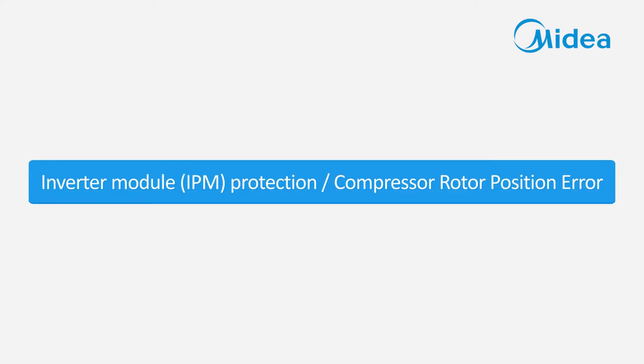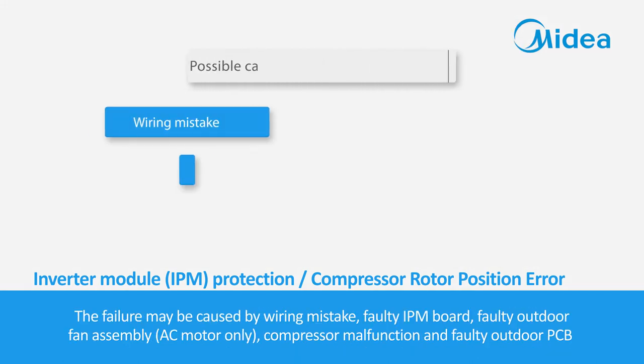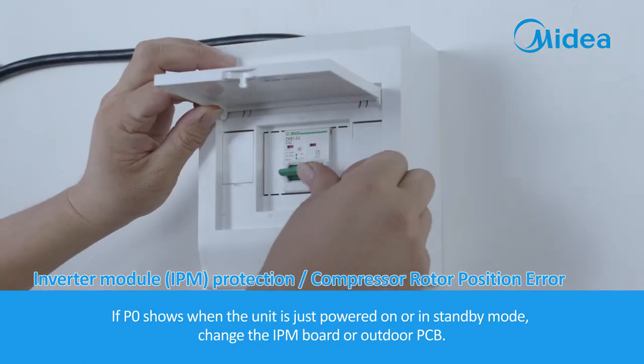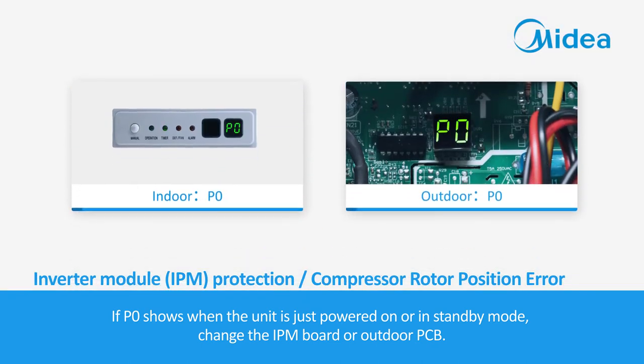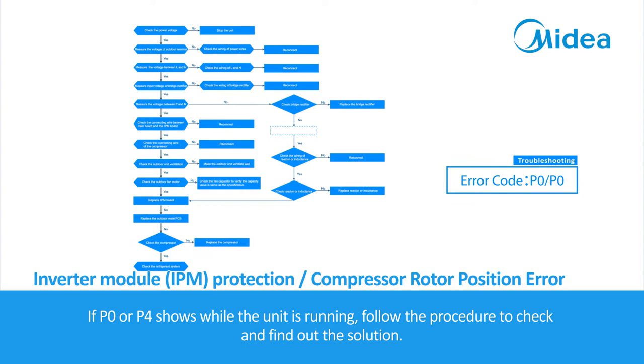Inverter module IPM protection and compressor rotor position error. Malfunction conditions: when the voltage signal the IPM sends to the compressor drive chip is abnormal, or the compressor feedback signal is abnormal, the display LED will show P0 or P4 and the AC will turn off. The failure may be caused by wiring mistake, faulty IPM board, faulty outdoor fan assembly (AC motor only), compressor malfunction, or faulty outdoor PCB. If P0 shows when the unit is just powered on or in standby mode, change the IPM board or outdoor PCB. If P0 or P4 shows while the unit is running, follow the procedure to check and find the solution.